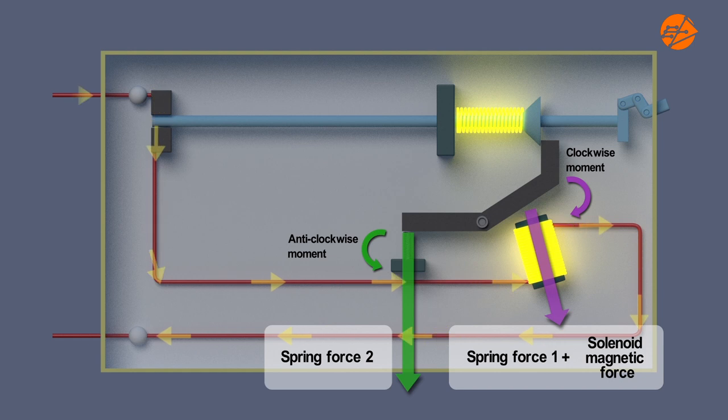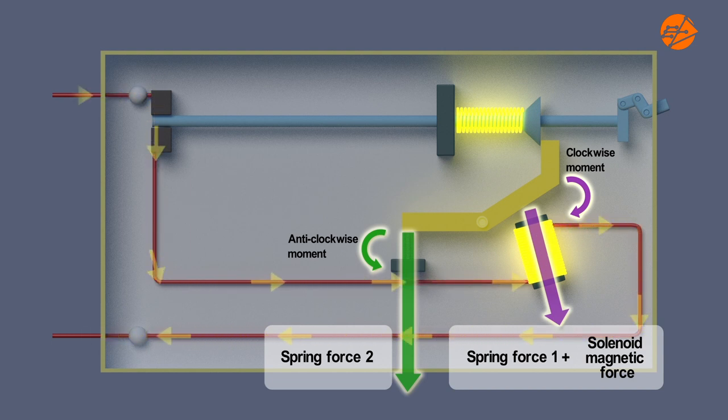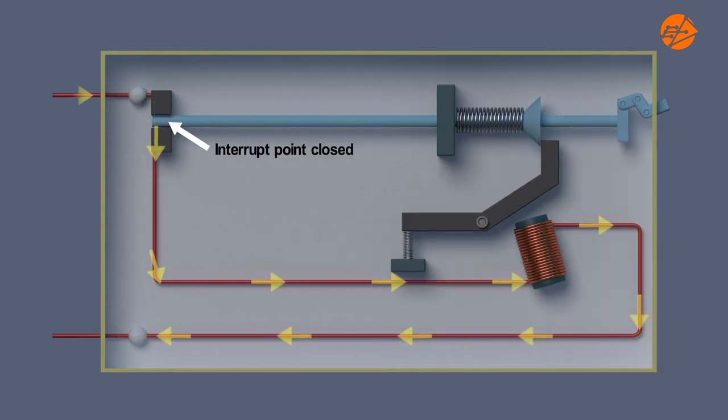Spring force 1 and the solenoid magnetic force is not strong enough to create a clockwise moment to overcome the anti-clockwise moment due to spring force 2 acting on the latch about the same pivot. The interrupt point remains closed and current flows normally through the circuit.